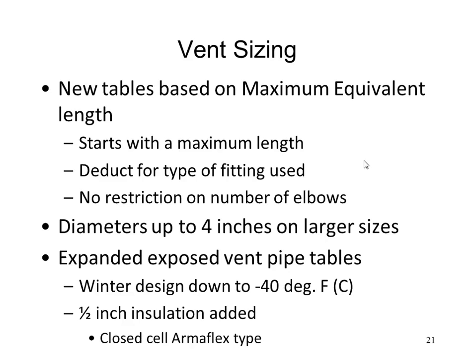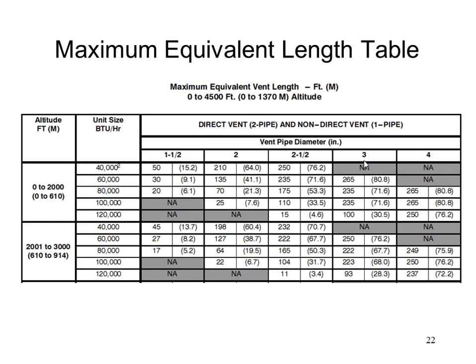On the venting, the rules for venting with this new modulating furnace are quite a bit different than the rules of previous furnaces, where we only could vent them 70 feet. These guys now can vent over 200 feet, and this drawing is actually even slightly outdated for these two modulating furnaces. They can actually go a few more feet than this, but this is a pretty safe number. And I didn't even bother showing you the rest of the table because all of our stuff, we're all at under 2,000 feet altitude in Chicago, so it doesn't really matter. So we're like 600 feet altitude.